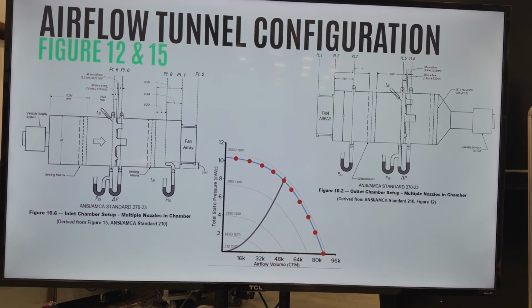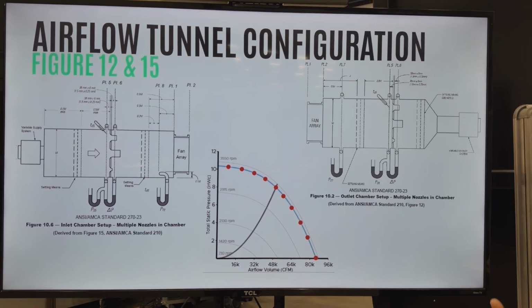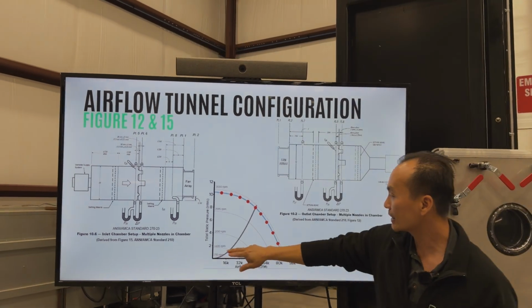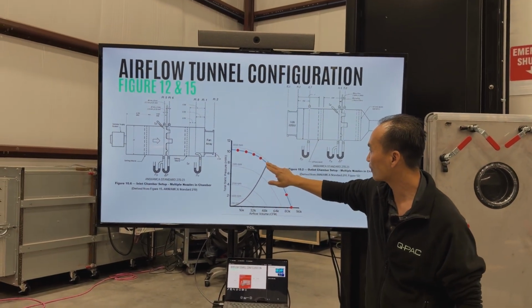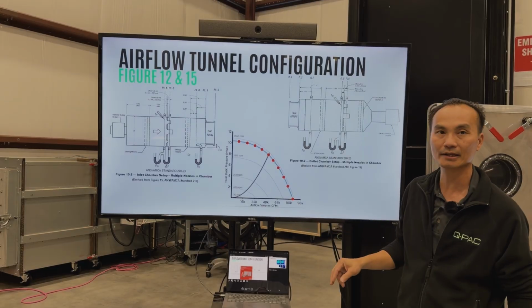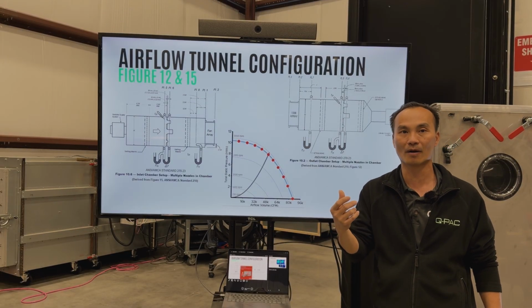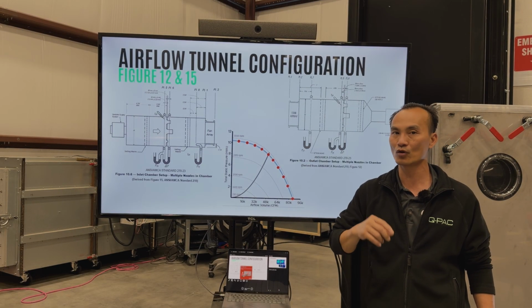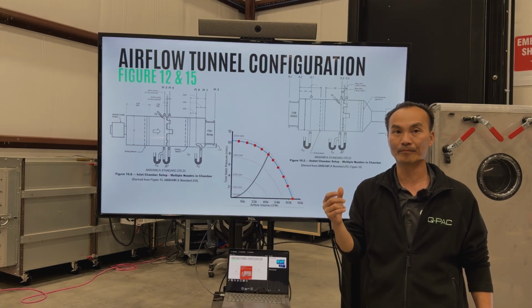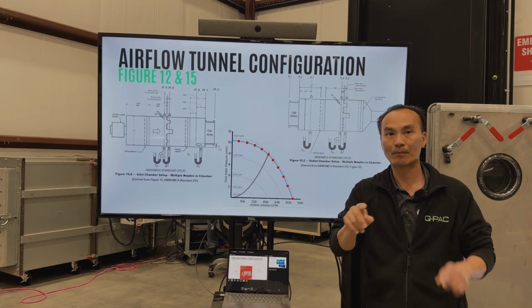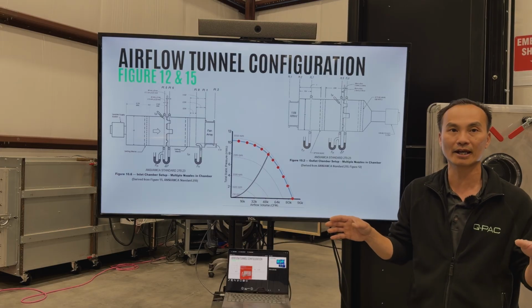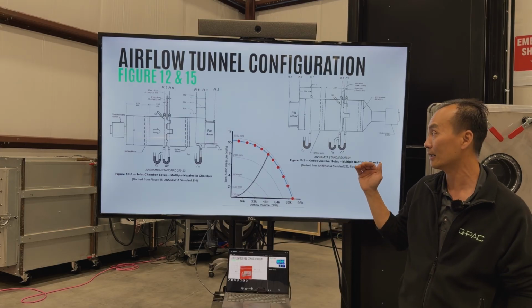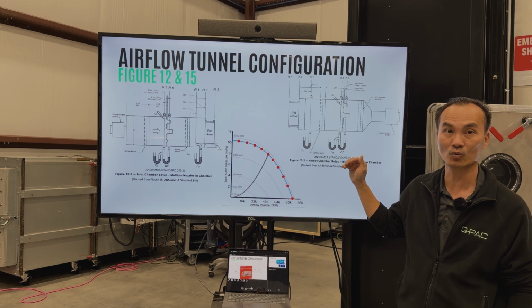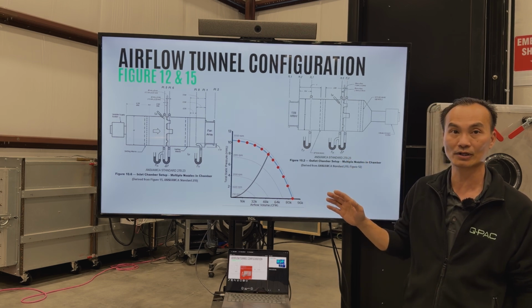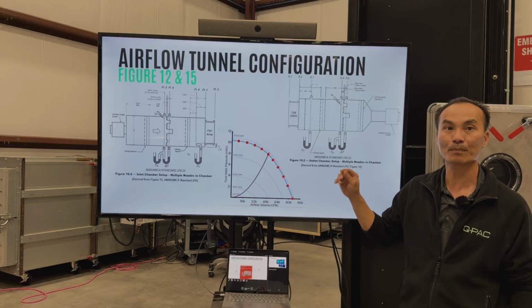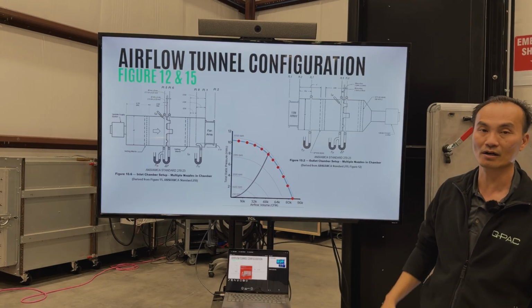The other unique feature that we built into this airflow tunnel is that it is able to identify how many points of testing are needed in order to fall within a certain percent of error. For example, if you want within 2% of error, how many points do you have to test, and all of this is fully automated by the airflow tunnel. So we don't have to do it. Most airflow tunnels today are manual, you have to pick the point and test it. This airflow tunnel picks its own points.